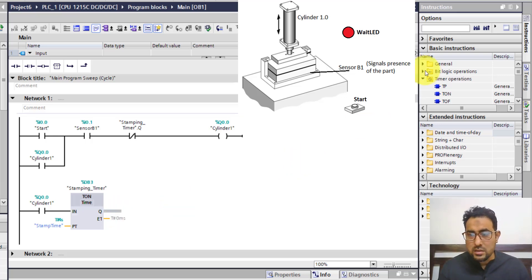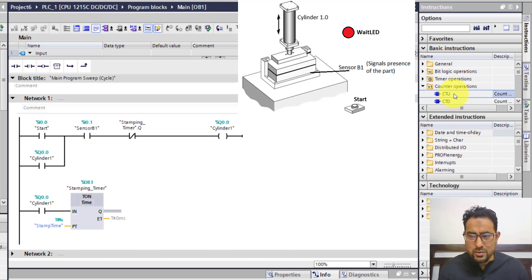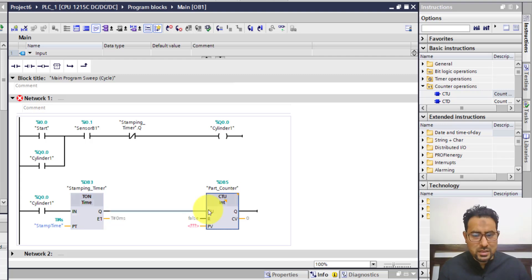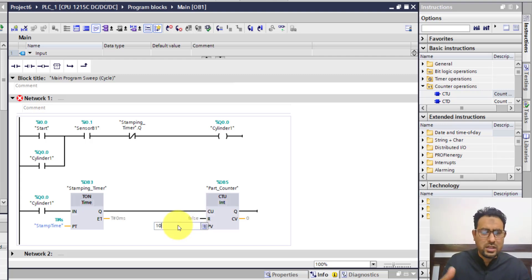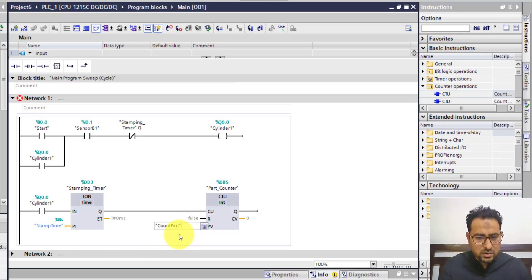So I need a counter. In the counter operations section, drop it down and you can see the counters available. I'm going to use the count-up counter — click and drag it. I'll name this counter part counter. Whenever this timer is done timing, the counter gets power and counts. For the preset value, we have already defined a constant named count part, so I can select that.